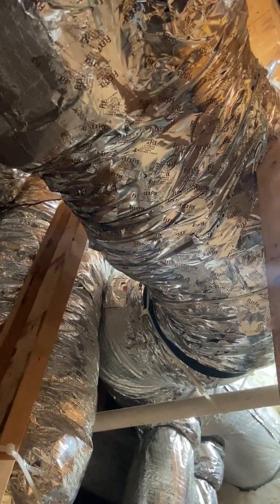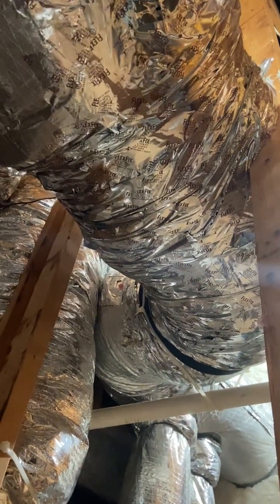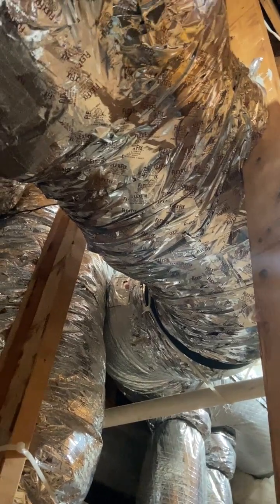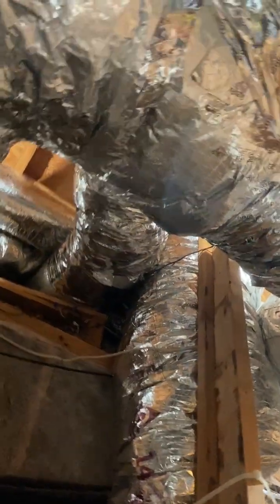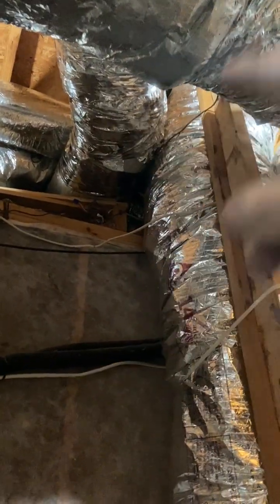So when a zone calls for heat like this one, it leaves that zone open and closes all the other zones. Now I have 3 zones. This is the main one right here, the big one, zone 1. Over here, you can see this guy coming off right there. It comes over and comes off the stack. That's the 3rd zone. And then finally, you can see up here coming off is the 2nd zone, and it goes down and runs along there. Okay, the main zone, and there is a valve. It's hard to see here, but I will show you some other zone control valves.